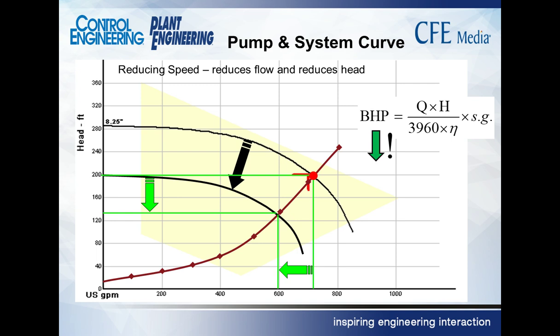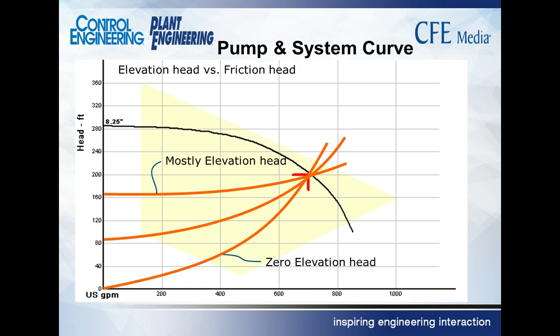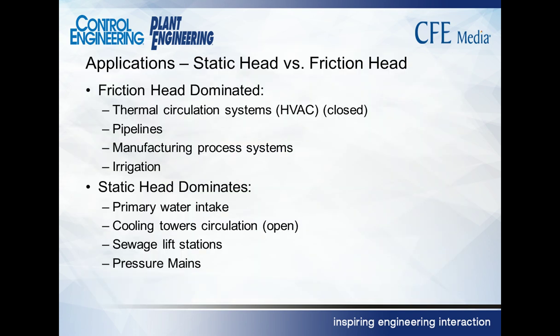Okay. Well, there are different types or different shapes for system curves. Most of them, virtually all of them, are bent in this direction because the friction increases exponentially, but some can be shallower than others. And the determining factor on that typically is how much static or elevation head you are pumping. So the pump curve on the bottom, marked zero elevation head, is probably a circulating system. And the one on the top, marked mostly elevation head, is something that's raising liquid up from one level to another. So here are some typical applications that help define that.